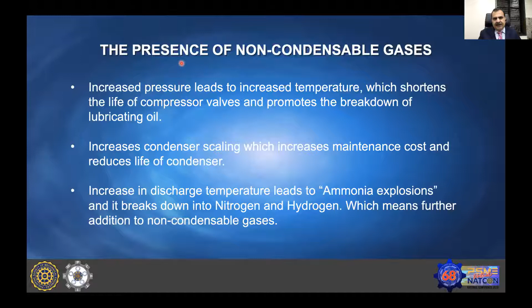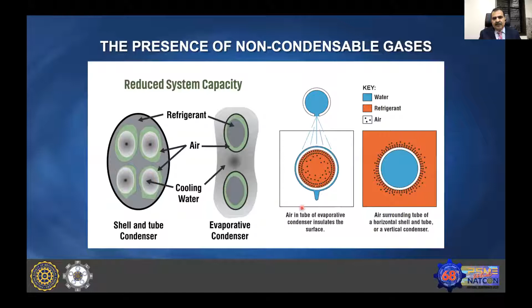Then, because of the increase in temperature, the condenser scaling increases, the maintenance of the condenser increases, and it reduces the condenser life and, of course, the performance of the condenser. And if the temperature keeps on increasing, it may lead to an ammonia explosion, and ammonia may break into nitrogen and hydrogen. We have NH3 ammonia breaking into 1 nitrogen and 3 hydrogen. So if they break down, both the nitrogen and hydrogen are non-condensable gases in our operating conditions. You can see here that the air gets accumulated on the tube side of your refrigerant, or on the outside of the tube. This generates a kind of insulation for the heat exchanger, and it reduces the performance of the heat exchanger.